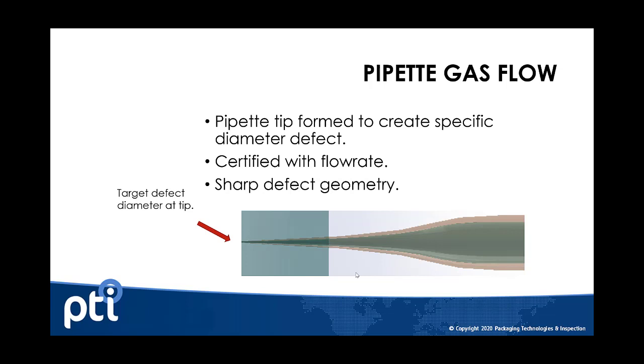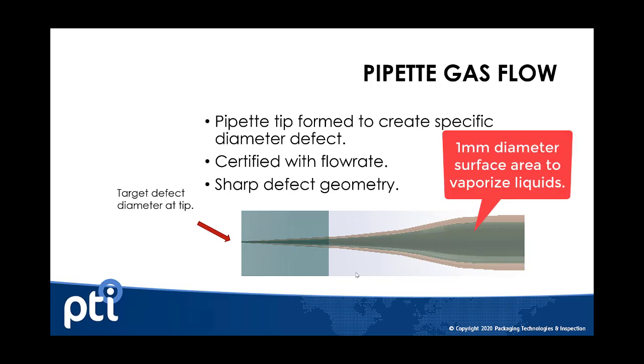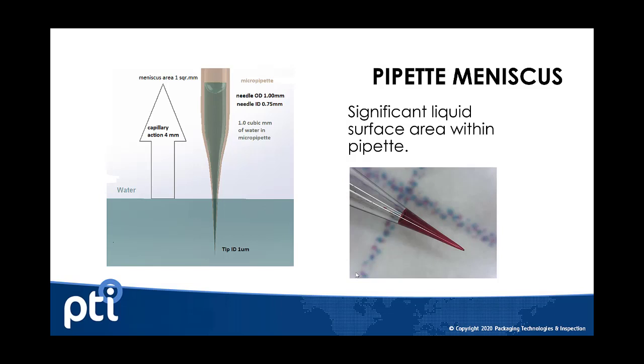A pipette, similar to a capillary, is an elongated tube. The difference is that the certified defect or very small defect is located at the tip of the pipette, which then flutes outward to a one millimeter internal diameter tube. A pipette is worse than a normal capillary because it draws liquid up into that fluted space, creating a larger basin for vaporization. So a pipette is even worse to use when validating a parenteral type application.